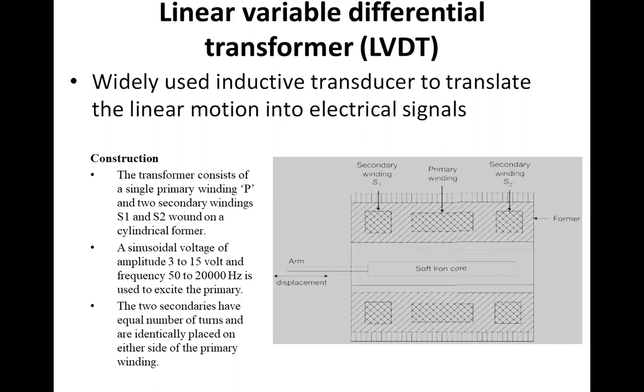Now the LVDT sensor works as follows. An LVDT measures displacement by associating a specific signal value for any given position of the core. This association of a signal value to a position occurs through electromagnetic coupling by an AC excitation signal on the primary winding to the core and back to the secondary windings.